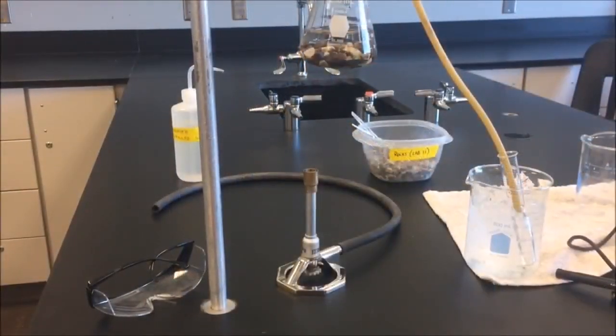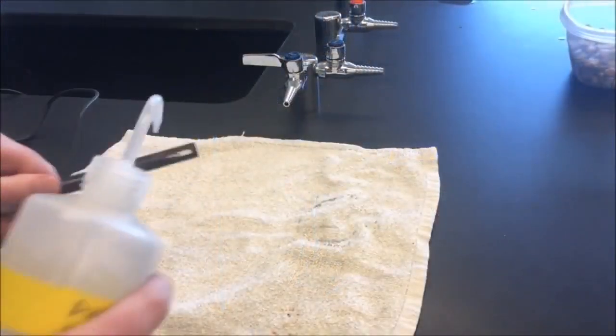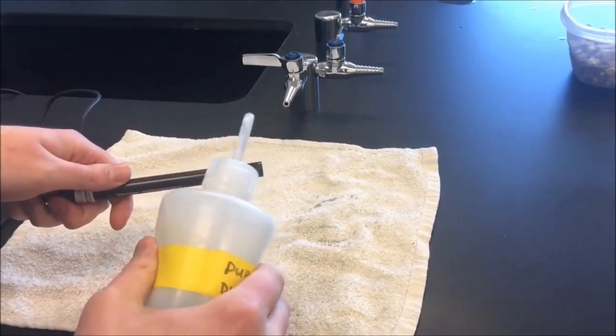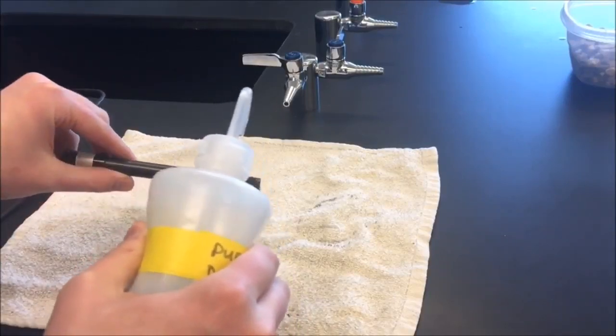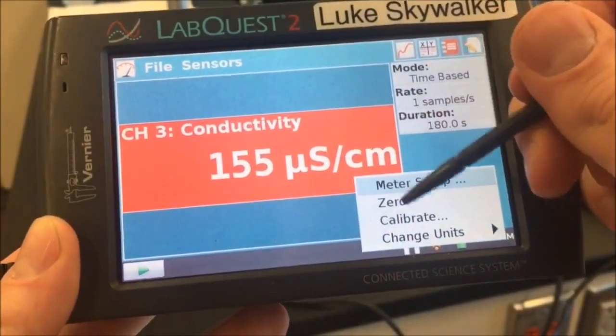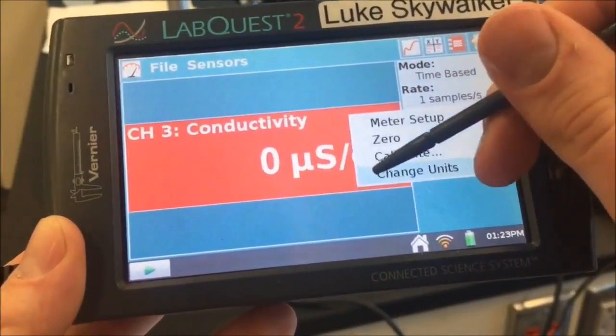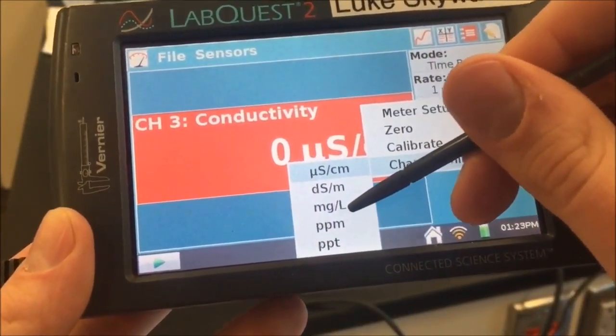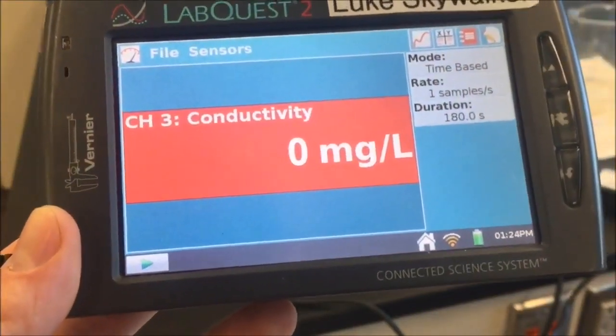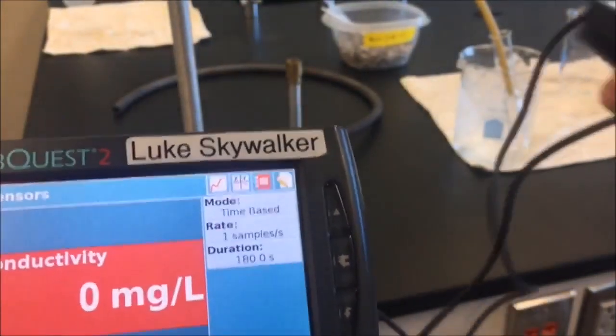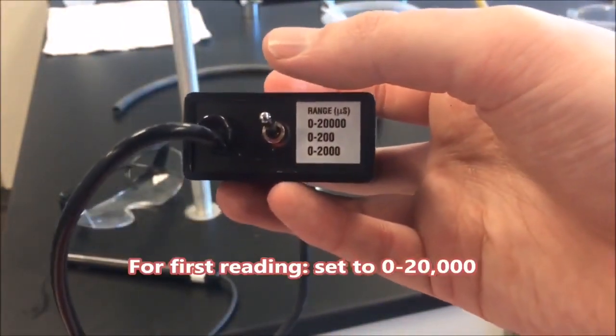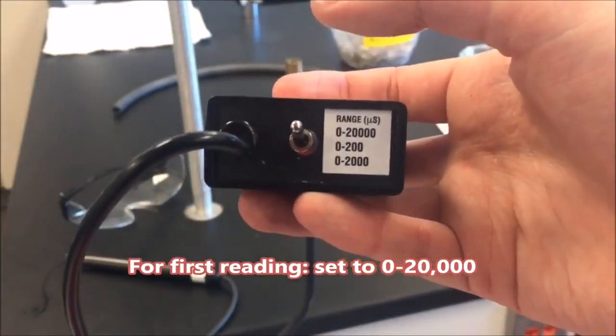Before we run the procedure, the first thing we need to do is measure how much salt is actually in the water. So what we're going to do first is plug our conductivity probe into the LabQuest device. Spray off your conductivity probe with distilled water. Before we take our measurement, we're going to make sure to change our units to milligrams per liter. And on the conductivity sensor, we want to make sure that we have it set to 0 to 20,000 initially.